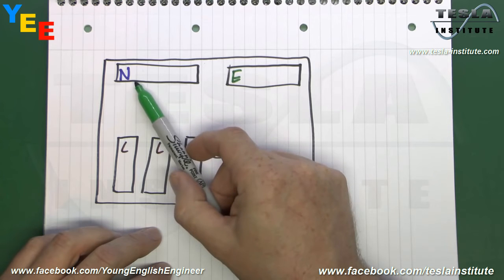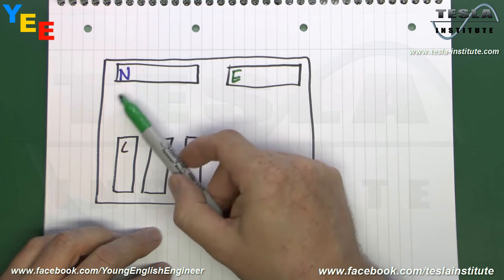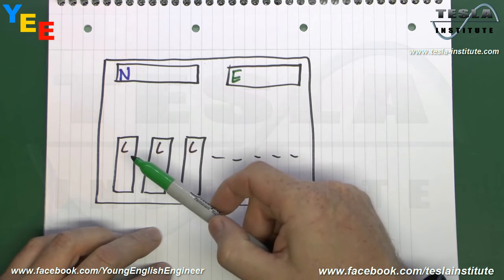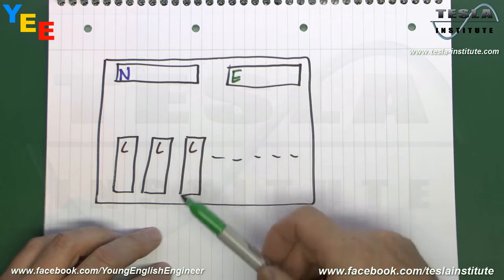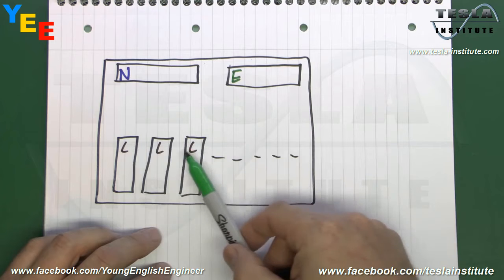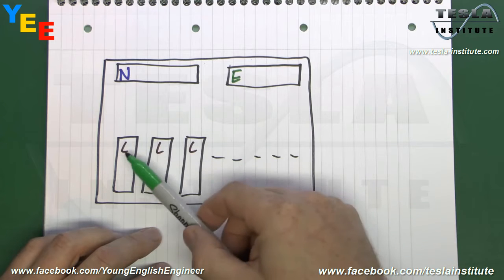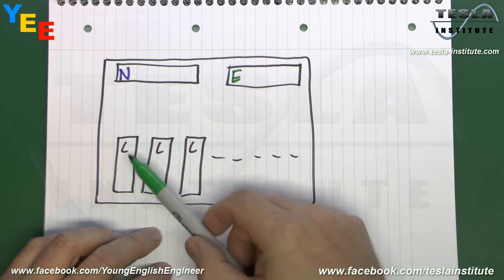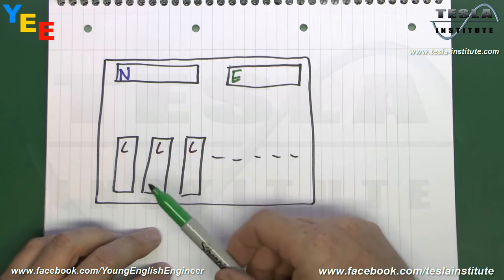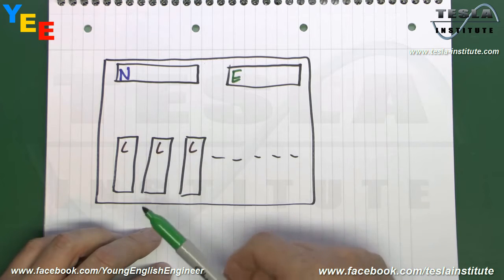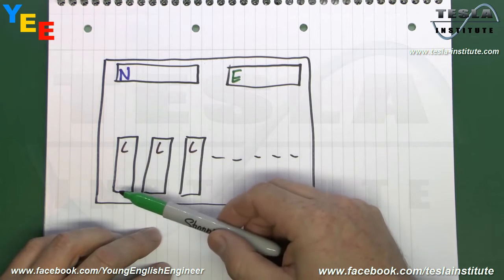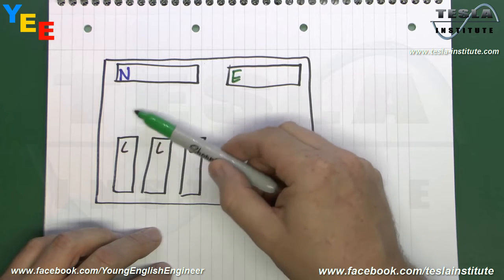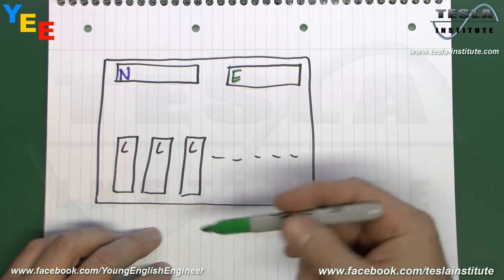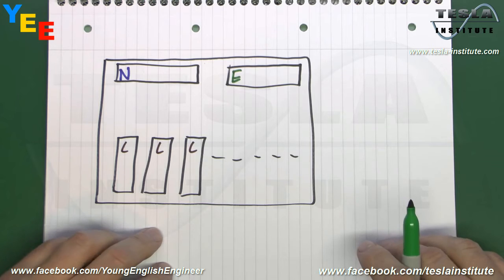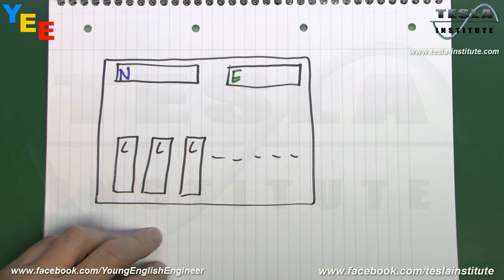First of all, if you left it connected to the neutral, then bearing in mind you've got all the other wires for the other circuits connected there, so clearly you need to remove that from those. And again with the line conductors as well, although you could turn off the circuit breaker, it's generally advisable to actually remove the wire from there. And if you had something say like an RCBO in here, again you'd have to disconnect the line and neutral from that device. Some of those can actually be damaged by applying 500 volts DC to them.